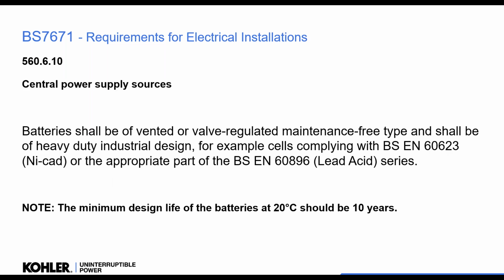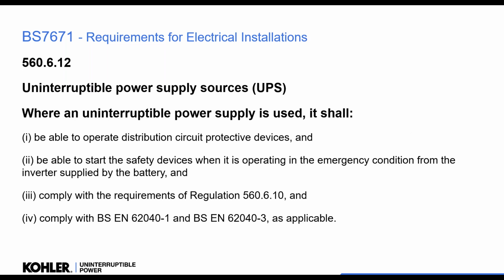So it also talks about the central power supply sources. It says the battery shall be vented or valve regulated, maintenance free, in accordance with the relevant standard, or for the NiCad, again, to the appropriate standard. So we can't just stick any batteries in, they do have to meet a certain standard. We should be designing the battery installations for 20 degrees and should be design lives of 10 years as well. But a lot of the regulations aren't doing enough to specify around the battery systems.